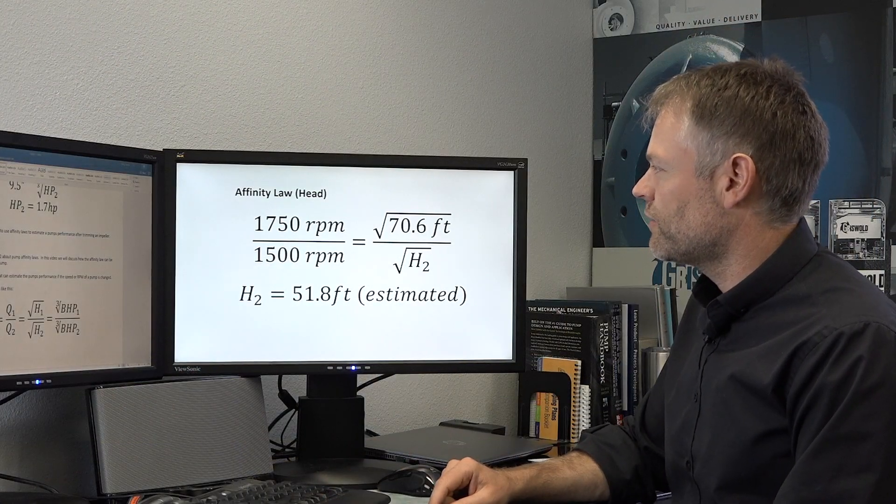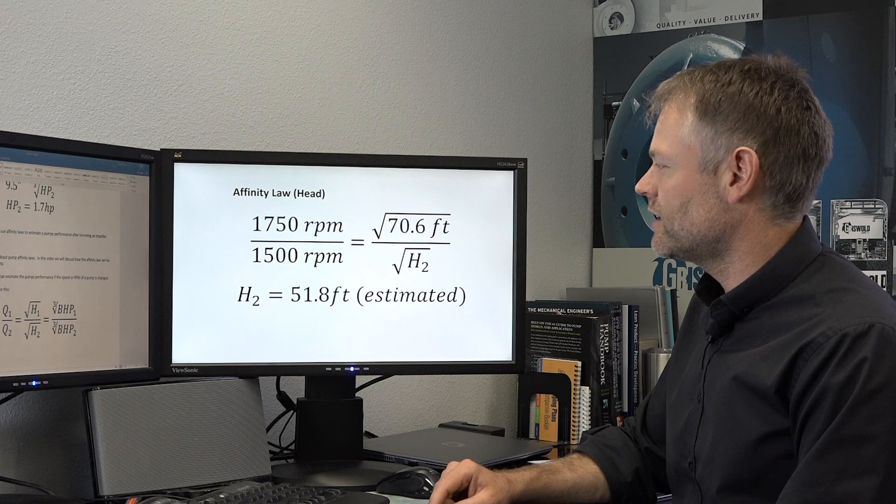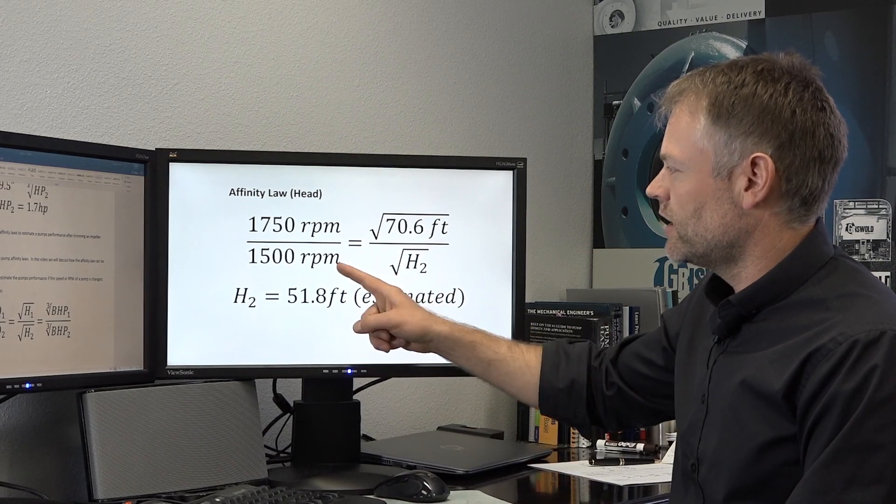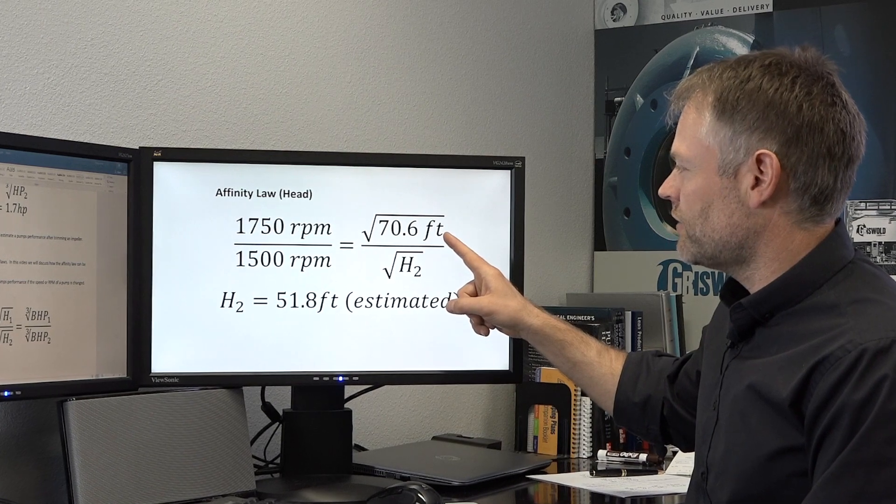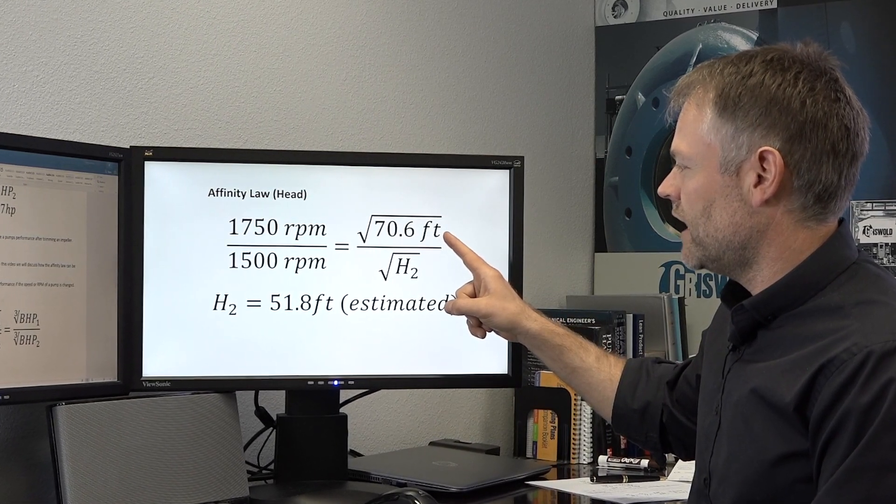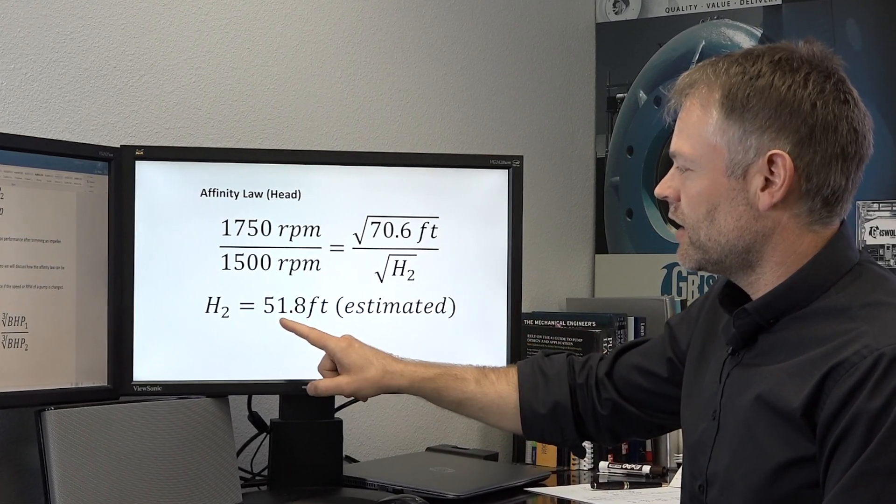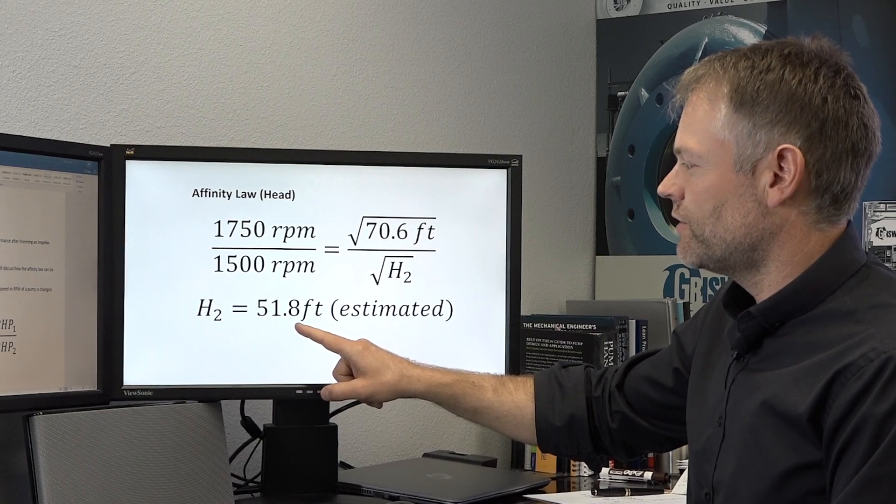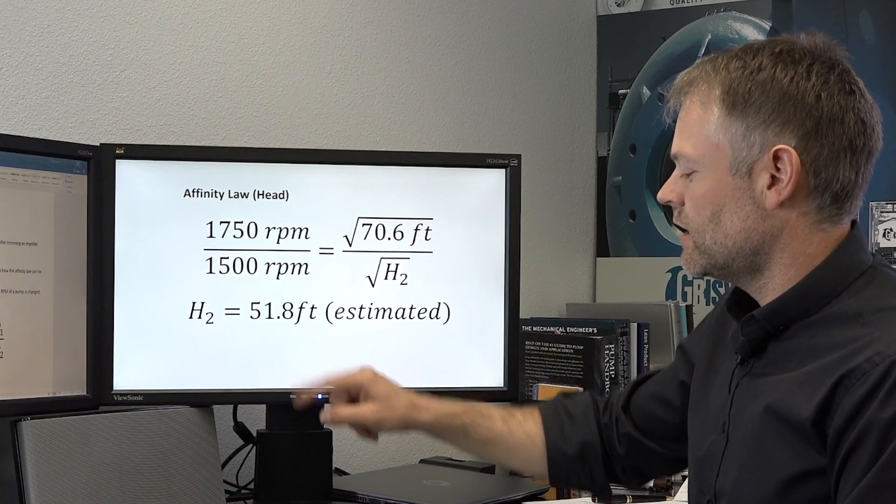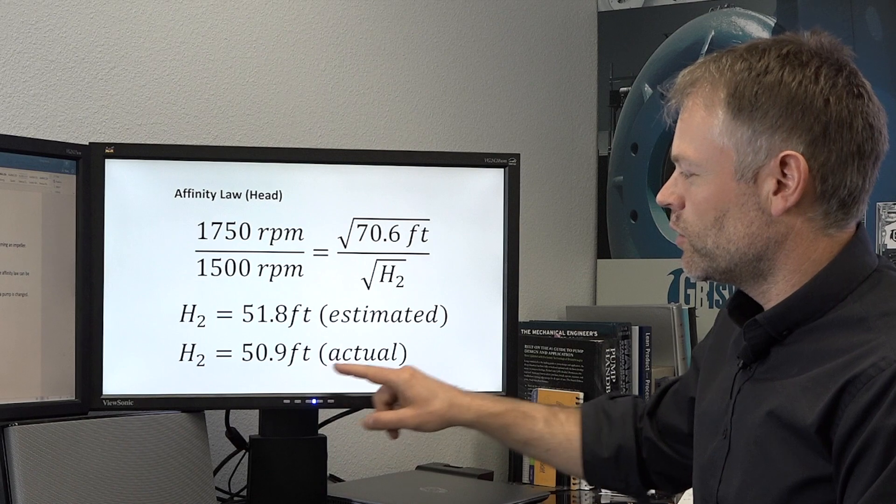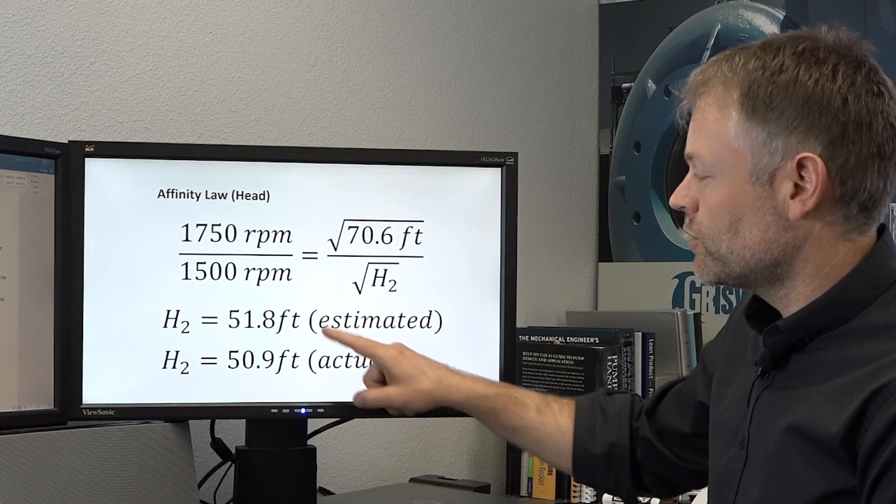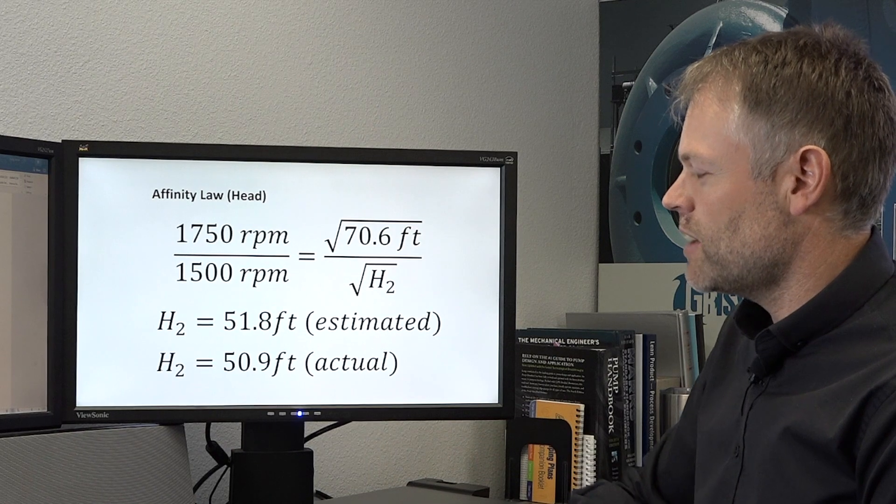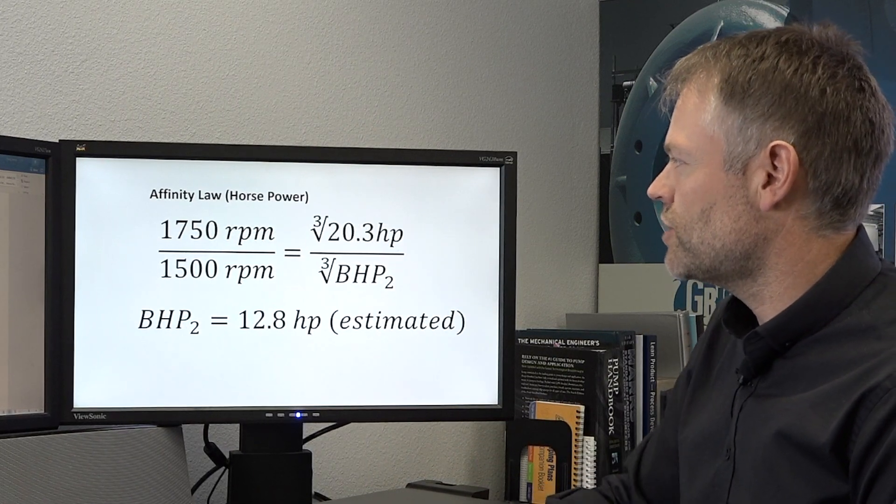Let's do a similar comparison for the predicted head. In this case we're going to include our change in speed. We started with 70.6 feet of head. The head is now estimated to have dropped to 51.8 feet, and when we were in the test lab we saw it actually at 50.9. So again, a very close estimation of how the pump's performance changes.